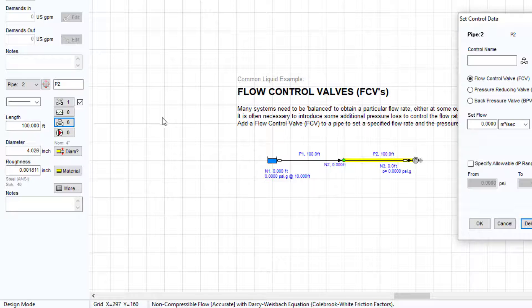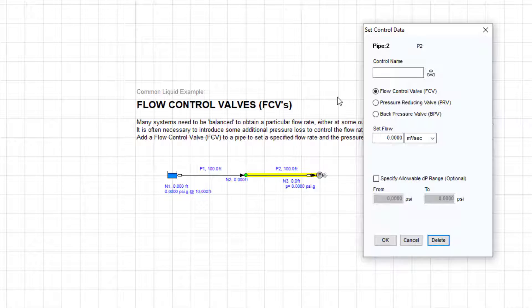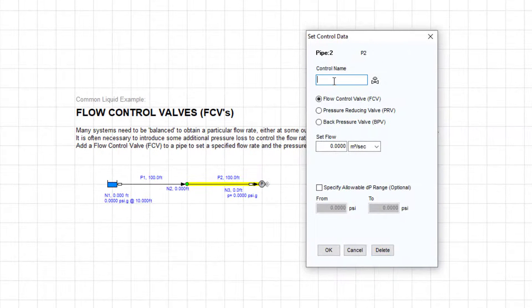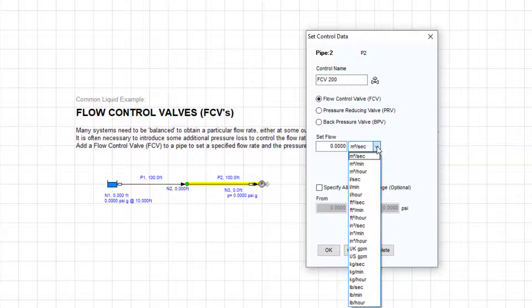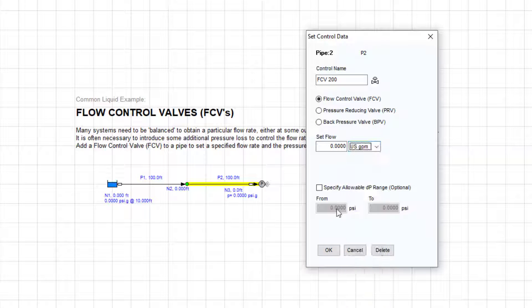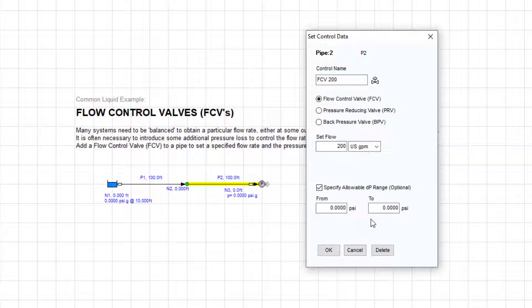First, looking at flow control valves, these are used to control the flow rate through a particular pipe. The user can enter the desired flow rate of, say, 200 US gallons per minute, and optionally define an allowable pressure drop range across the valve.